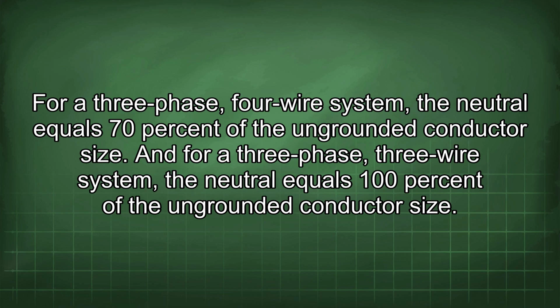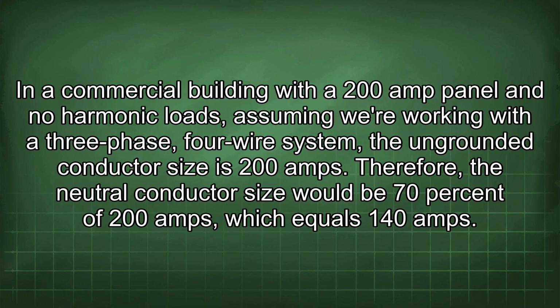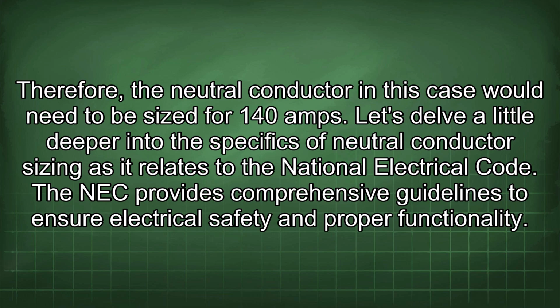And for a three-phase, three-wire system, the neutral equals 100% of the ungrounded conductor size. In a commercial building with a 200 amp panel and no harmonic loads, assuming we're working with a three-phase, four-wire system, the ungrounded conductor size is 200 amps. Therefore, the neutral conductor size would be 70% of 200 amps, which equals 140 amps. Therefore, the neutral conductor in this case would need to be sized for 140 amps.